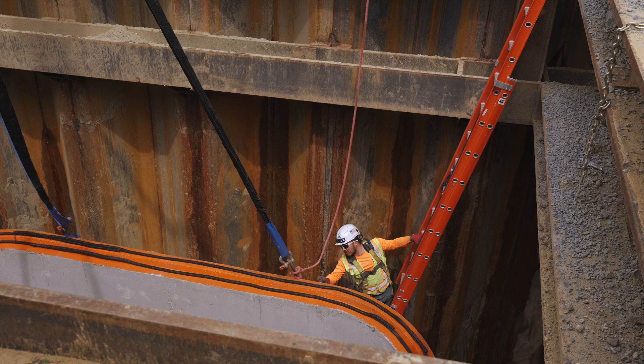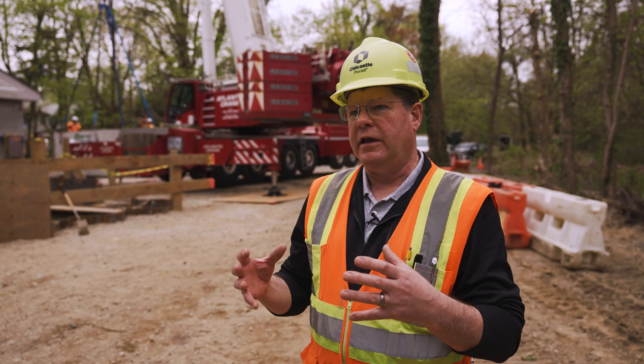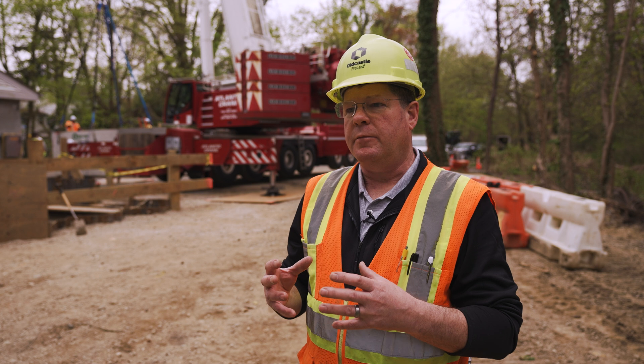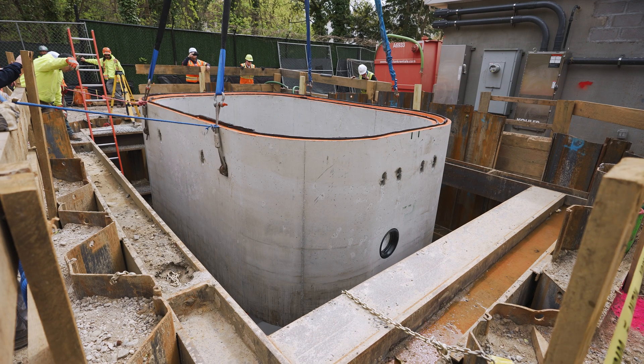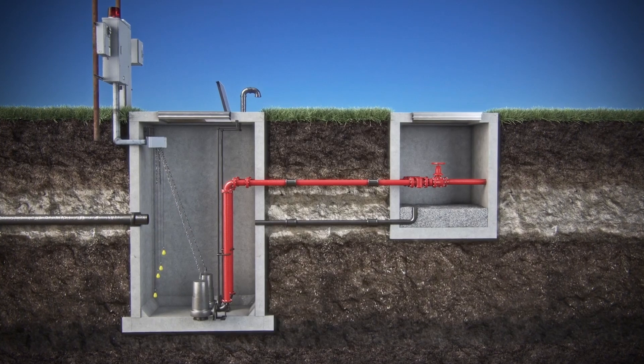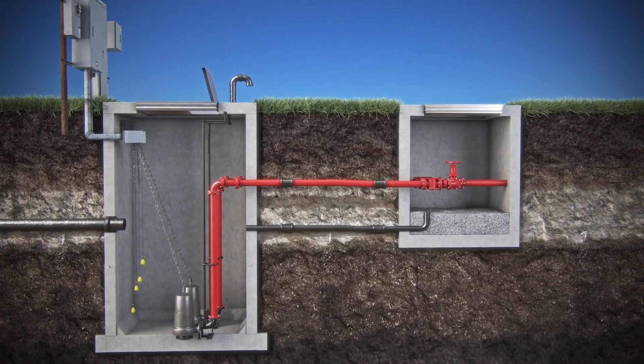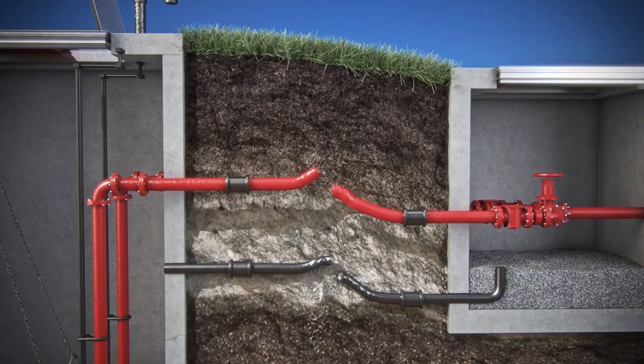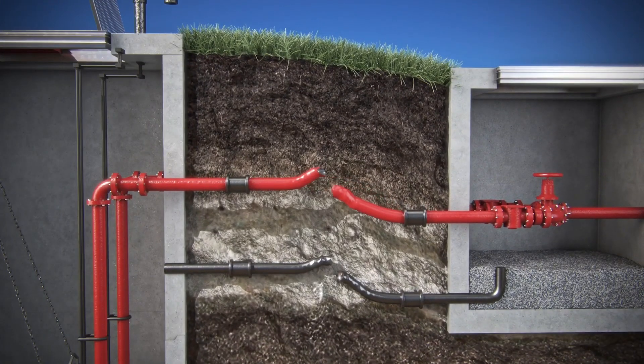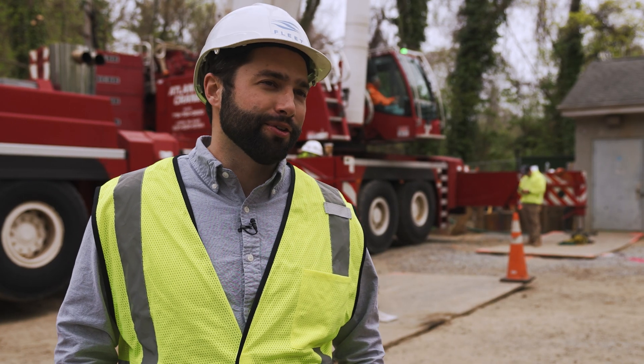The conventional pump station is two structures — a valve vault and a wet well. What we're doing is putting these two together to make it a smaller structure and an easier, safer installation for the contractor. It also avoids differential settlement between the wet well and the valve vault. Those two structures settle differently, and the pipe running between them has to make up for that settling, which has led to many issues in the past. With the one-lift, we don't have those issues.